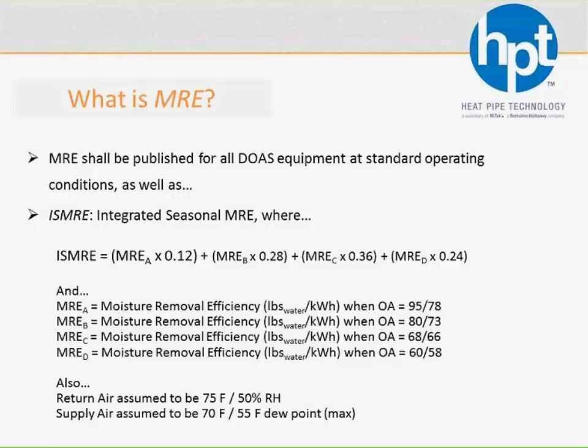It also assumes that the return air is coming back at 75 degrees and 50%, and that the supply air is going to come off the coil at a maximum dew point of 55 degrees and be warmed up to 70 degrees. So whatever supplemental heat is needed to get it up to 70 is going to be factored in to tell you what your MRE is going to be, as well as your ISMRE.